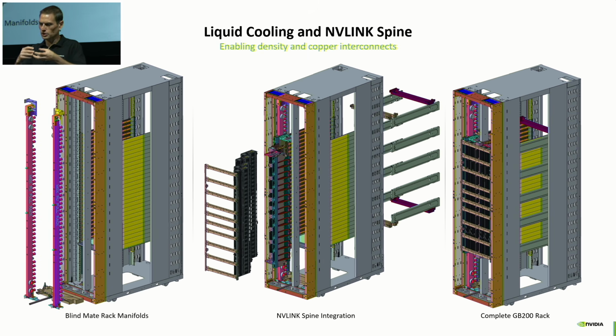So they're spring-loaded, they can float, they can reliably mate, but we have to generate enough force to actually plug them together, and that force is substantial. Adding up every connector, every cable cartridge, every QD, we end up with 6,500 pounds of mating force in the middle of that rack, in that 27U span. To put that in context, that's more than a lot of cars—I Googled it, it's actually the curb weight of a Chevy Tahoe parked there in the middle of the rack.